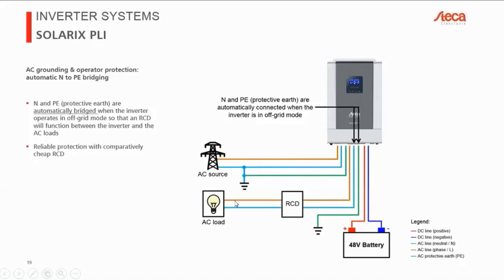On the AC output, we have our loads connected to the live wire and the neutral wire, potentially also connected to the ground depending on your load. Sometimes you need it, sometimes you don't. And here you have your residual current device. And here, basically the connection between neutral and ground is made as soon as the inverter is switching to off-grid mode automatically.